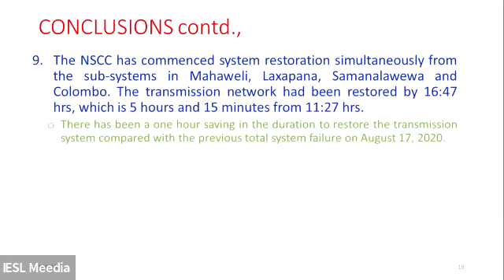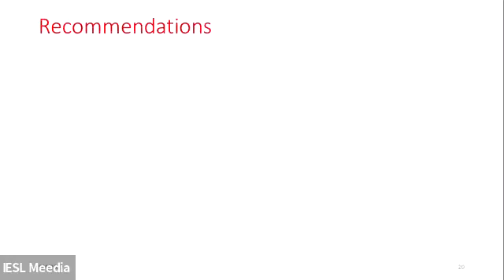And once the system collapsed, the National System Control Center did a good job in trying to bring the system back by parallel operation of Mahaweli, Laxapana, and Samanalawewa, and ultimately they managed to restore the transmission network in 5 hours and 15 minutes, which is 1 hour gained as compared to the blackout on the 17th August 2020. So these are the conclusions, and based on that, we made some recommendations.